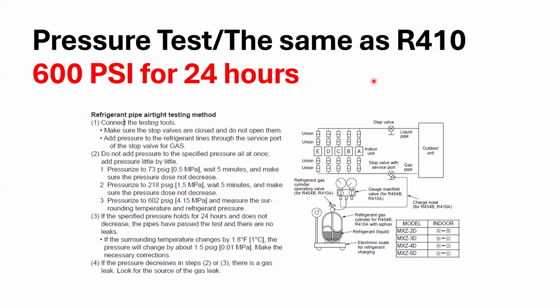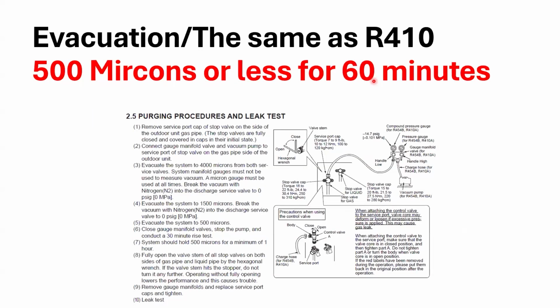Heat the compressor with a heat gun. 500 microns or less for 60 minutes. Let's go back to that. So again, run it down below 500, 300, whatever, and then pumps off for 60 minutes and it's going to rise most likely to some number, but we don't want it to rise past 500.